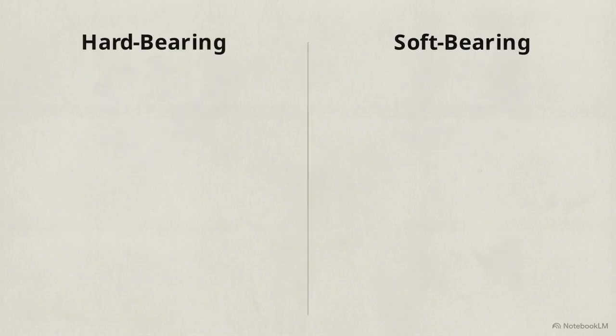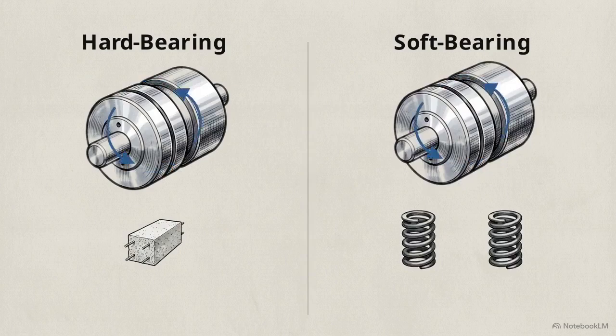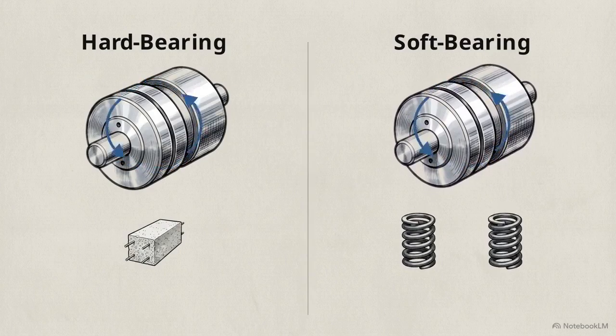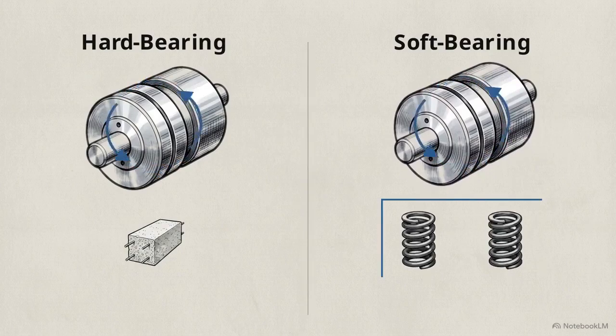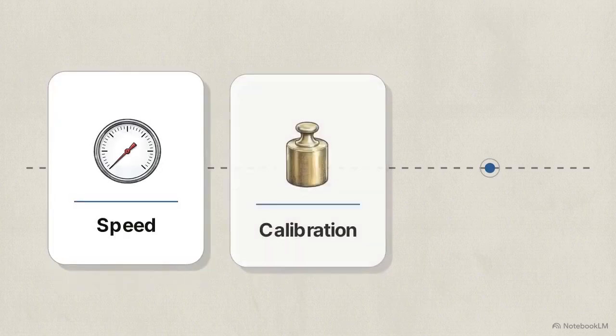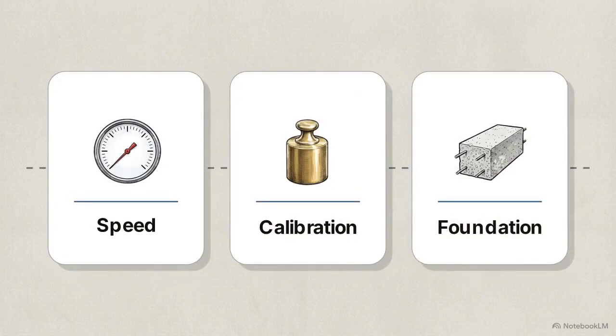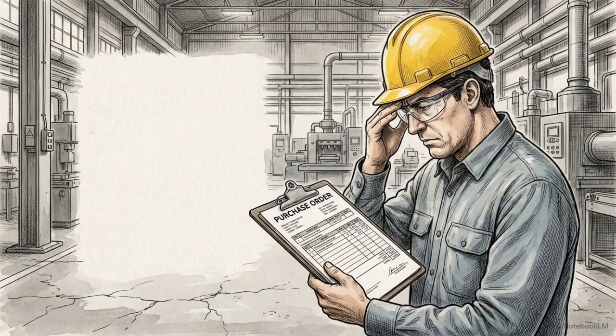The terms soft and hard refer to the physics of the internal support structures. The rotor is either anchored to a solid, immovable block or cradled by a dynamic, expanding spring system. This single design choice sets the parameters for the machine's speed, calibration, and even the type of floor it requires.